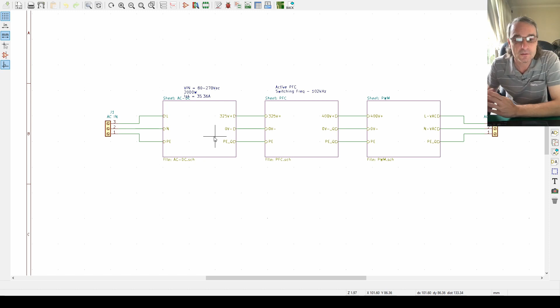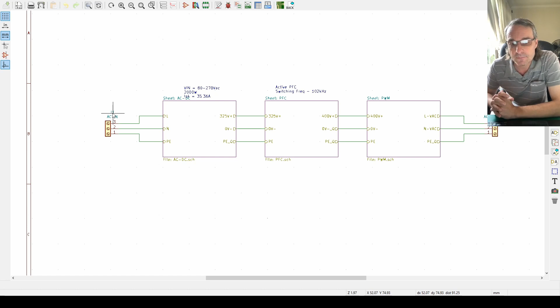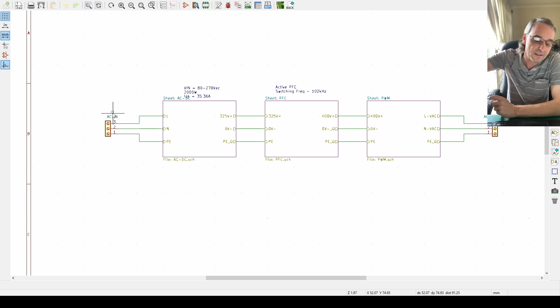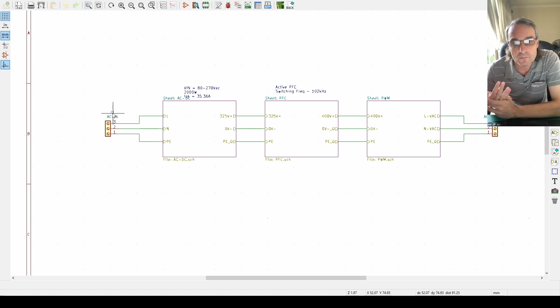So anyway, coming back to our circuit, we have our AC in, basically a live, a neutral, and an earth. They will have to give me an earth reference, obviously. This live and neutral normally in an MCC is derived from the control transformer, so they will maybe have a 525 volt 3-phase AC busbar system, and they will put in a step-down transformer, which they normally do anyway, and that will take 525 down to 110 volt AC, and they will give me the 110 volt AC with live, neutral, and earth. What I thought was, let's design this for a universal input.